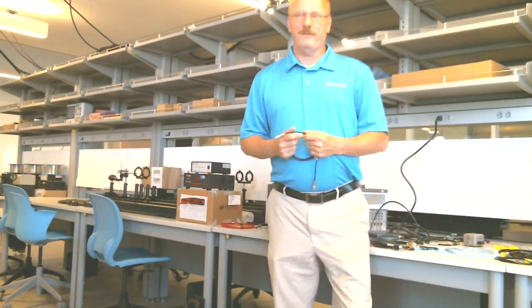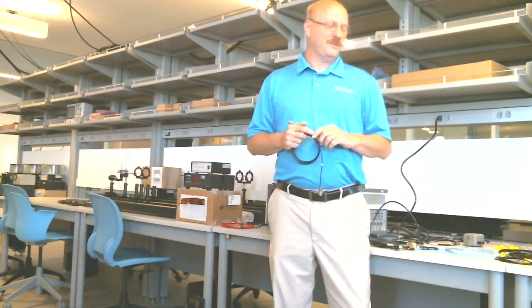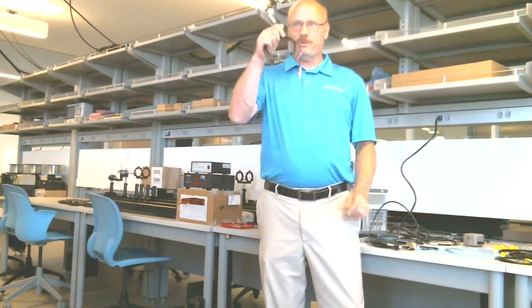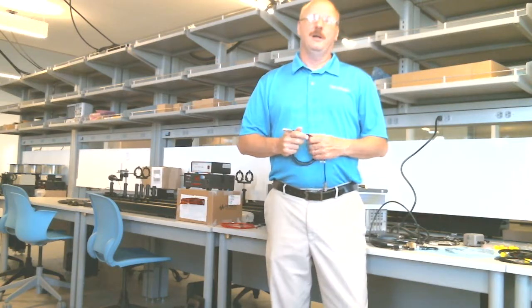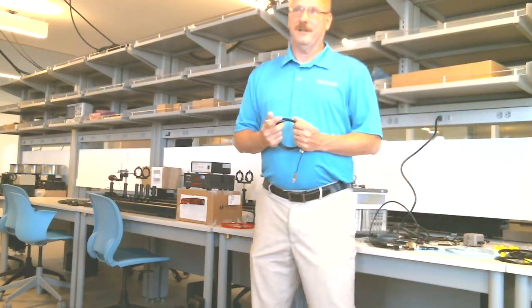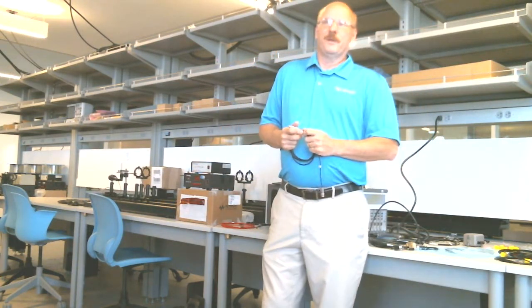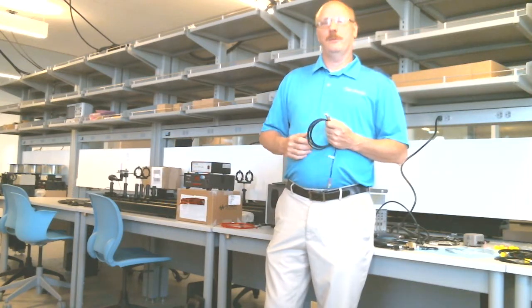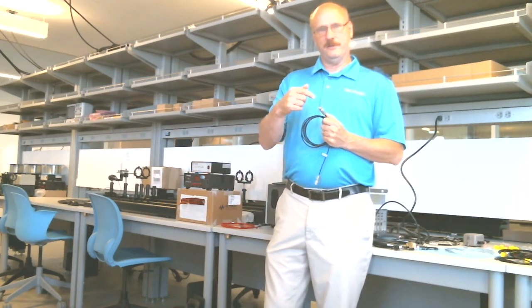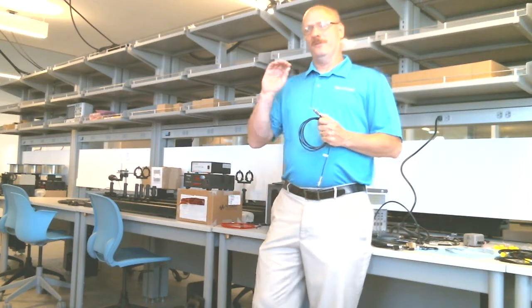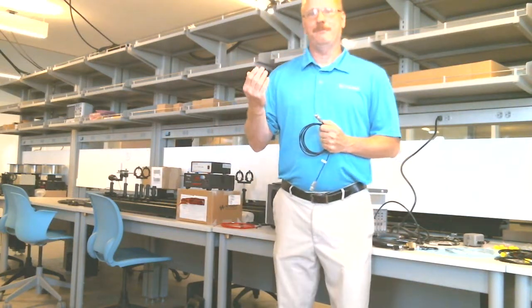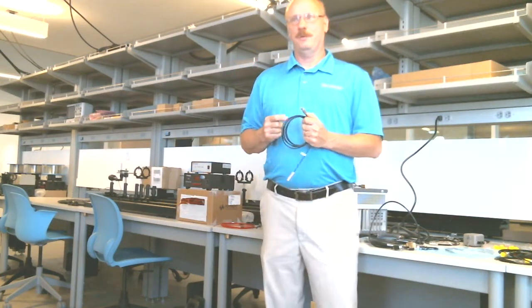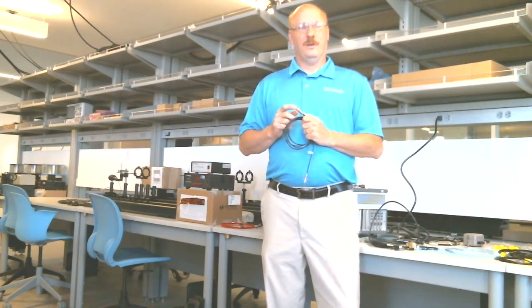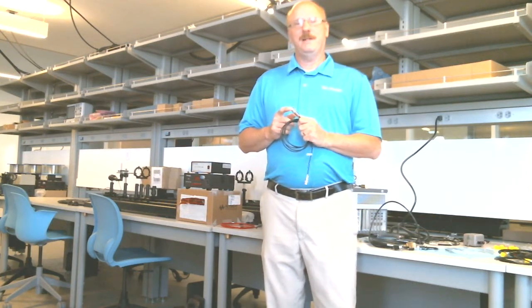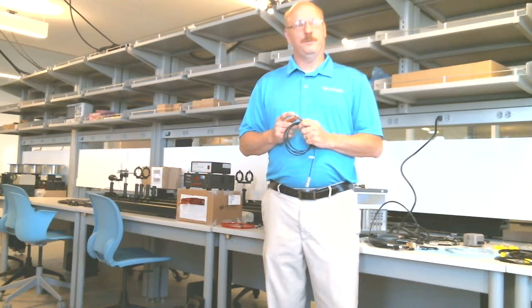But if I use what's called guarding, which this system is set up for, just by plugging this in it enables that feature because it senses you've connected a guard-capable cable. By using guarding, when I source a voltage to that center conductor, I'm also going to take that voltage, turn it around, and put it into a unity gain buffer internally in the SMU, and drive the guard with that. So what that means is I'm going to have 0 volts across my cable.